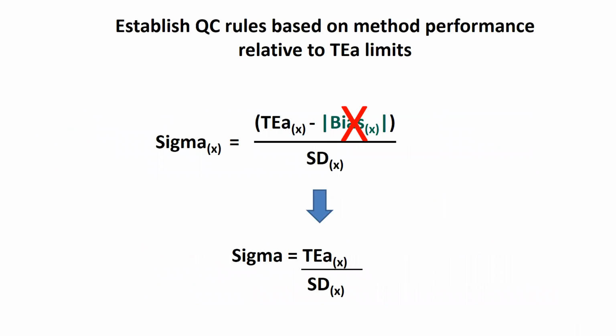Another way to prevent clinically significant errors is to ensure the QC alert rules are set appropriately to catch errors before they become clinically significant. One strategy is to base the rules on the sigma metric. The sigma metric relates the analytical performance, or bias and imprecision, to allowable total error as shown by this equation. For QC, the bias is typically set to 0 because we want to detect a change from the QC target mean. So that can be discounted.